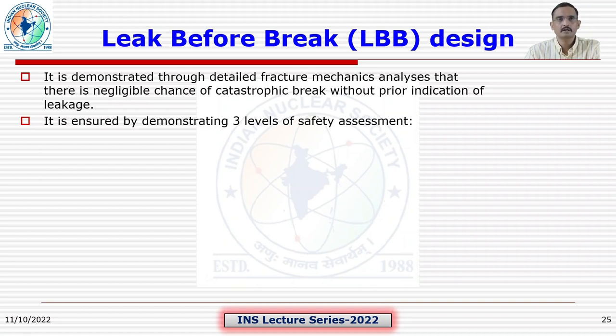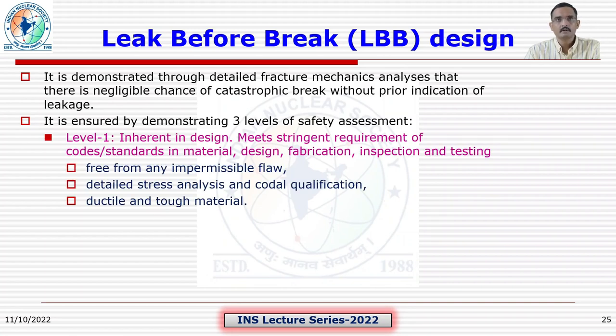It is ensured by demonstrating three levels of safety assessment. Level 1 is inherent in design, where the material meets stringent requirements of codes and standards in material design, fabrication, inspection and testing. This ensures the material is free from any impermissible flaw, through detailed stress analysis, codal qualification of the components, and selection of ductile and tough material. All these parts are taken care of as part of level 1 leak before break qualification.